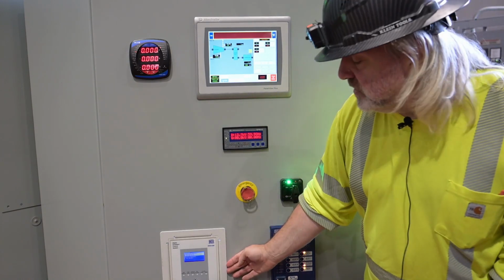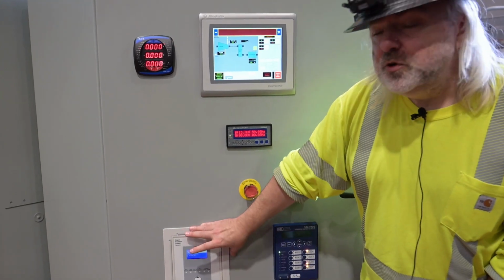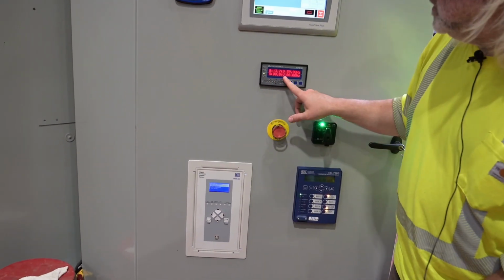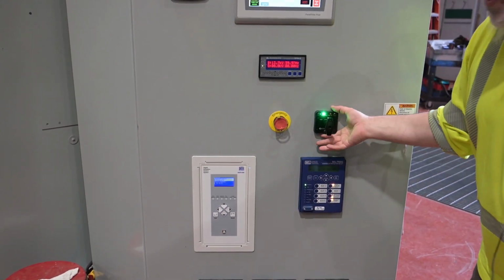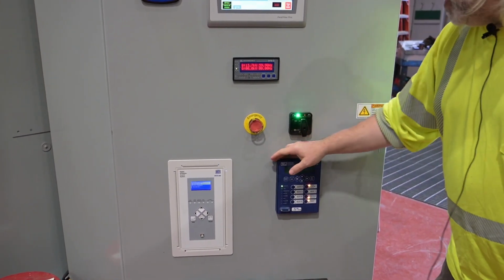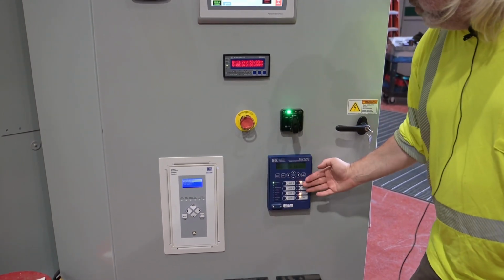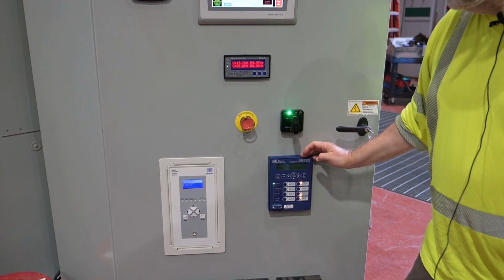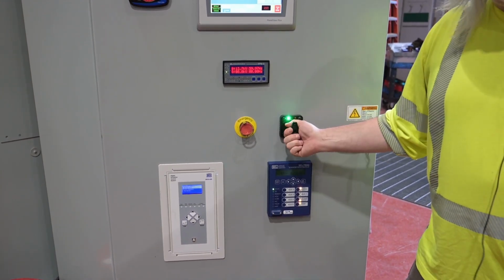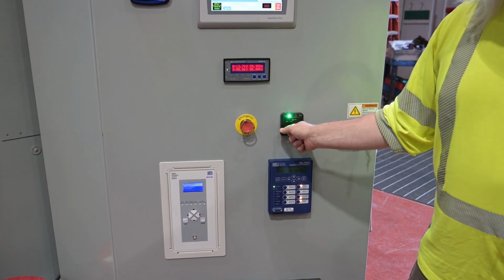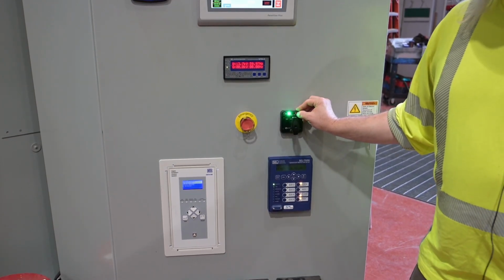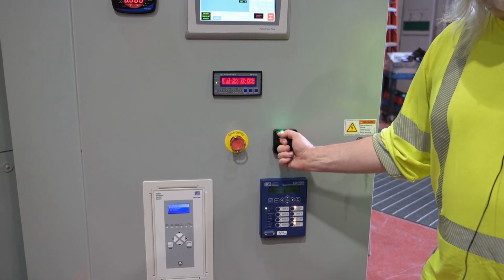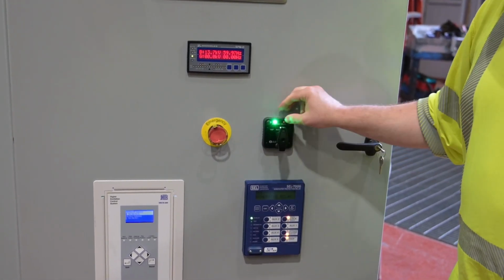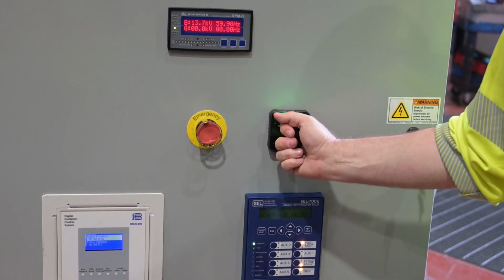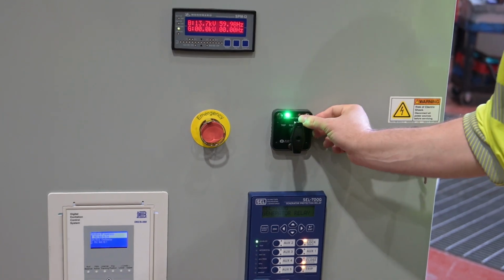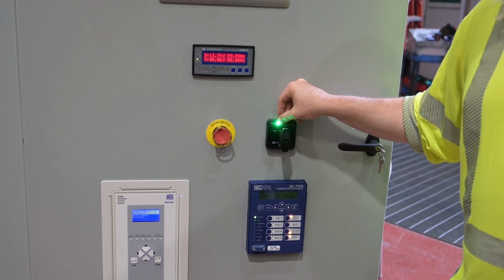Here is our Basler DECS-250 voltage regulator. This is used to control the excitation, the voltage of the unit. Over here we have our lockout relay. This relay is actuated from our generator protection relay, this unit in blue. If it decides that we are outside protected settings, it will trip the unit by causing this lockout relay to trip. When this lockout relay is tripped, an active trip will have this light be red. If this light is red, you cannot reset the handle. Do not try and reset the handle. Both lights have to be off for you to be able to reset. Once both lights are off, the protection is clear, we can reset, and the relay will be green.